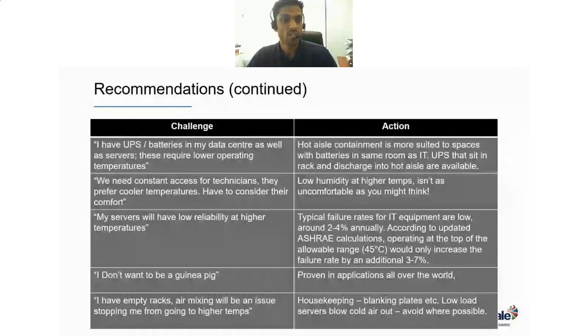Next point, we need constant access for the technicians. They prefer cooler temperature, and we have to consider their comfort. First of all, data centers are not for human comfort. The cold aisle in a data center, which you keep at 24 or 25 degrees, is perfectly okay for human comfort. When it's a hot aisle, which is probably like 35 degrees, the humidity level is not so high. So the dry bulb temperature is high, but the humidity is very low, which is not as uncomfortable as you think.